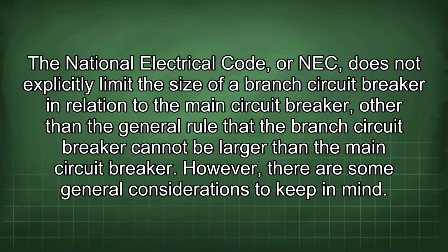The National Electrical Code, or NEC, does not explicitly limit the size of a branch circuit breaker in relation to the main circuit breaker, other than the general rule that the branch circuit breaker cannot be larger than the main circuit breaker. However, there are some general considerations to keep in mind.